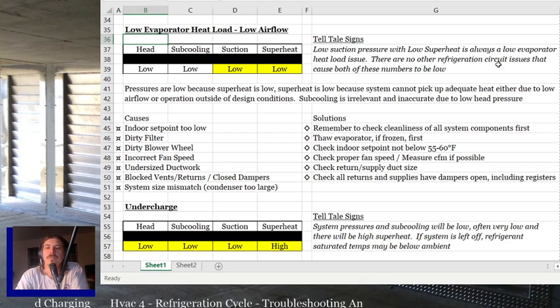If you actually hit freezing, then you start to form ice on the coil, and you start to get even less airflow because the ice is taking up space on the coil. So that makes your superheat even lower to non-existent, which helps form more ice, which causes lower airflow, which makes it worse and worse and worse.